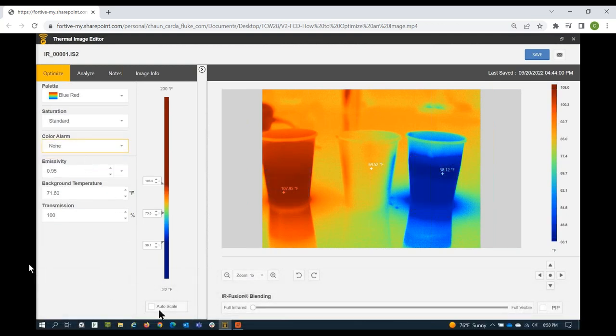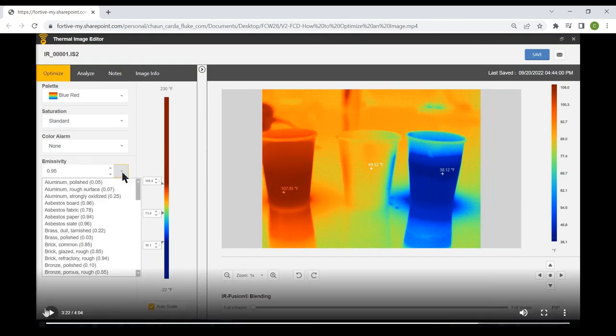We set color alarm to None, check Auto Scale, and move on to Emissivity. Everything emits thermal radiation, but not everything emits energy the same way. Low emissivity surfaces like shiny metals can reflect infrared energy from other objects and throw off your image and measurement accuracy. Use this option to select the type of material you were imaging — polished aluminum, strongly oxidized aluminum, asbestos, brass, brick, bronze, and so on — to properly set the emissivity for the image.